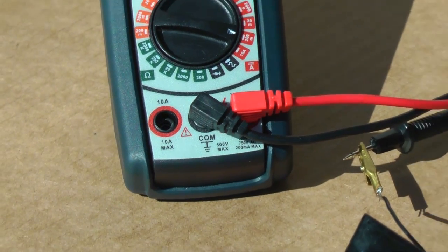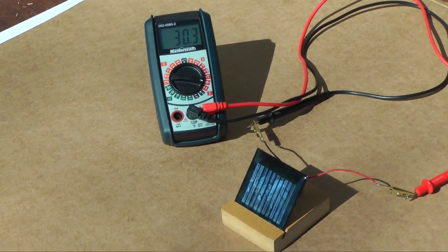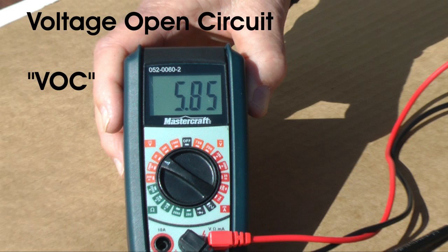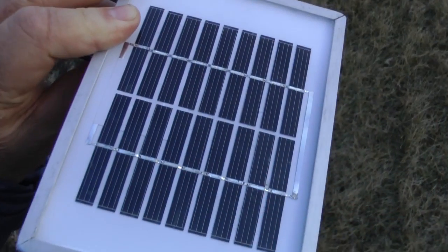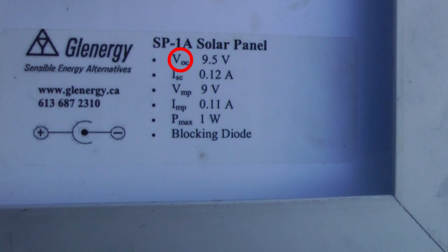This type of voltage and current reading have a special designation in the photovoltaic industry. The voltage reading we took is designated VOC or voltage open circuit. No load is connected to the panel. The current reading is designated ISC or current short circuit. This is the maximum amperage the panel produces under standard light conditions. If you look at the back of a professionally made panel, you will see a ratings document with values for VOC and ISC under standard light conditions.